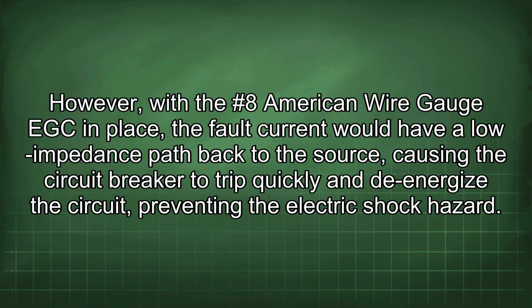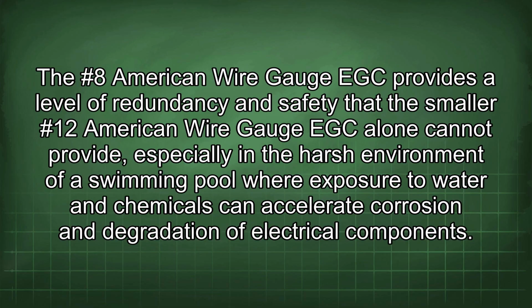However, with the #8 American wire gauge EGC in place, the fault current would have a low impedance path back to the source, causing the circuit breaker to trip quickly and de-energize the circuit, preventing the electric shock hazard. The #8 American wire gauge EGC provides a level of redundancy and safety that the smaller #12 American wire gauge EGC alone cannot provide, especially in the harsh environment of a swimming pool where exposure to water and chemicals can accelerate corrosion and degradation of electrical components.